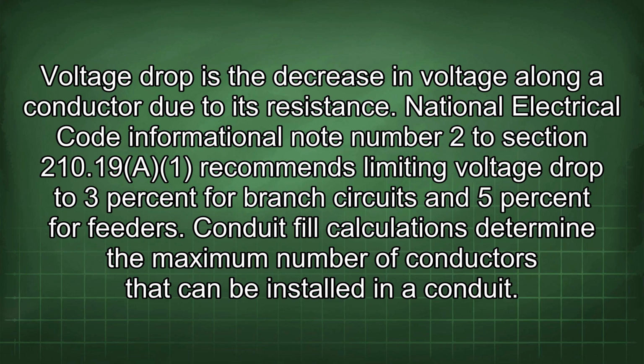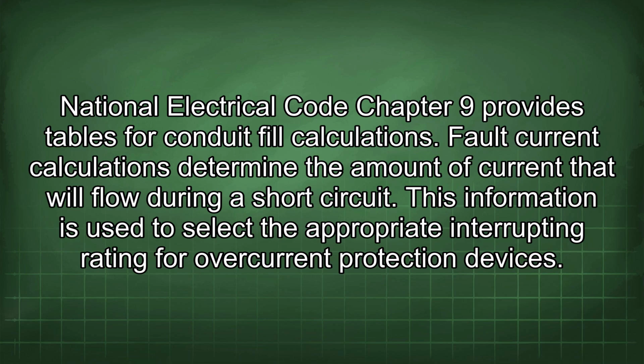National Electrical Code Informational Note No. 2 to Section 210.19(A)(1) recommends limiting voltage drop to 3% for branch circuits and 5% for feeders. Conduit fill calculations determine the maximum number of conductors that can be installed in a conduit. National Electrical Code Chapter 9 provides tables for conduit fill calculations.